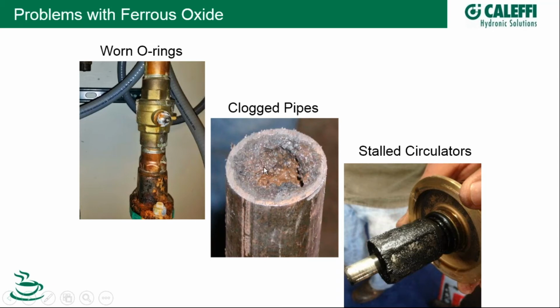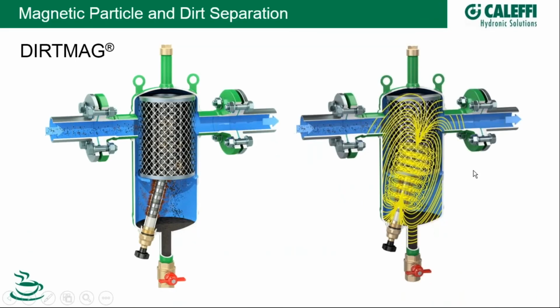O-rings, it likes to be sticky, so clogged pipes, and because it's magnetically attracted to magnets, here is an ECM circulator whose rotor was pulled out, and we can see it stalled, and we can see magnetite here. So as a result of the ECM magnets on that rotor attracting the magnetite, eventually she stalls out.